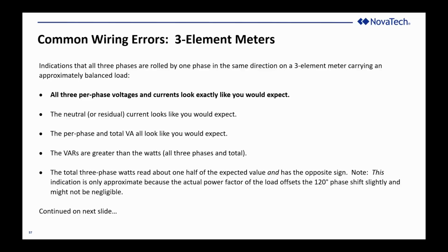Okay, so all three are rotated in the same direction. All three phase voltages and currents look exactly normal. The neutral current looks like you would expect. The per phase and total VA look normal. The VARs are greater than the watts. Okay, so here's the first thing that you're going to see that looks a little fishy. Typically, you're usually operating with pretty good power factor, so the watts are going to be substantially greater than the VARs. If you've rotated the phases, the VARs will be greater than the watts. The total three-phase watts will read about half of their expected value, and it'll have the opposite sign. That's because the cosine of 120 is 0.5.